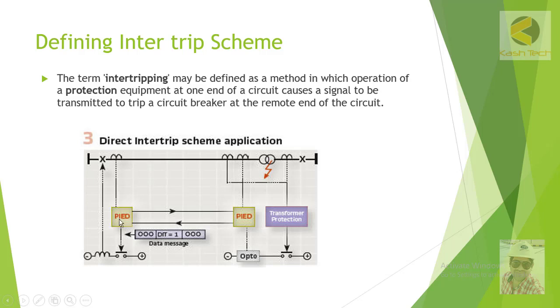This type of scheme is called a direct transfer trip scheme. If there is a fault at substation B and there is no breaker locally, we want to immediately trip the feeding breaker at the remote station. Through the protection device, a signal is transmitted and as soon as the signal is received, it trips the breaker at the remote end to cut the fault current.